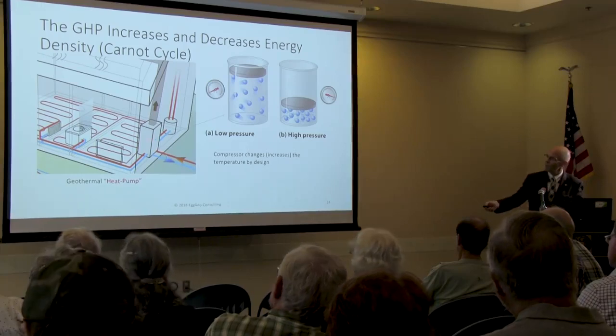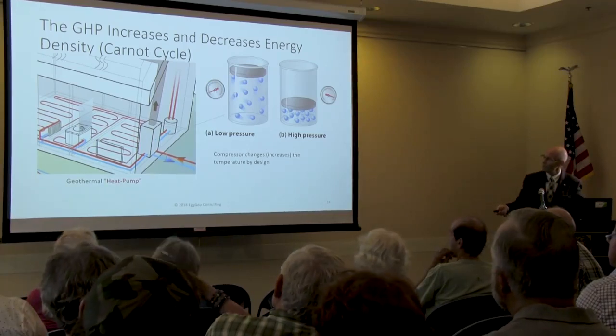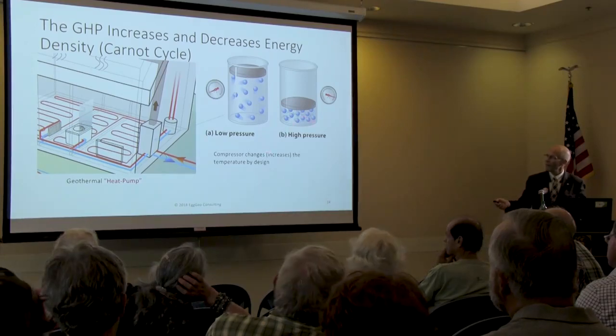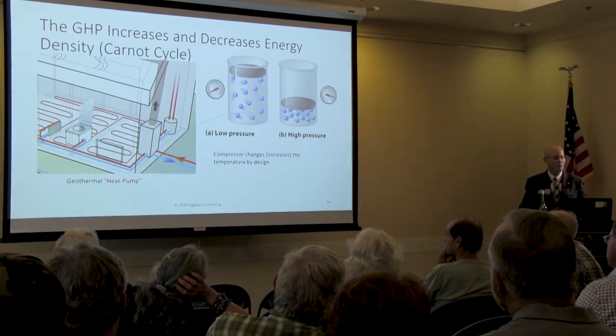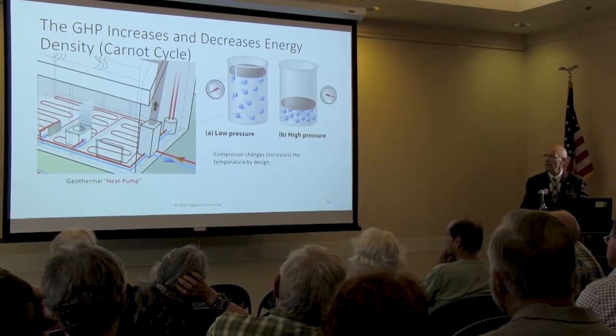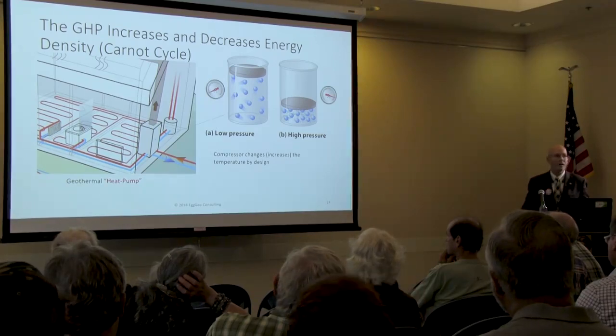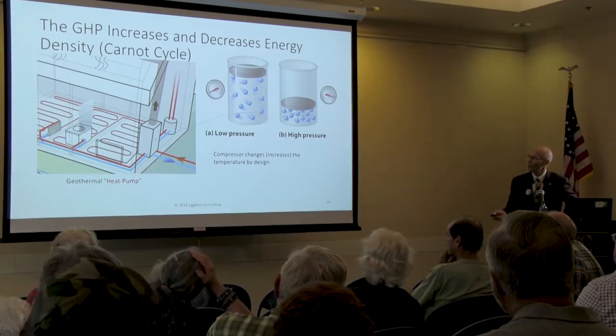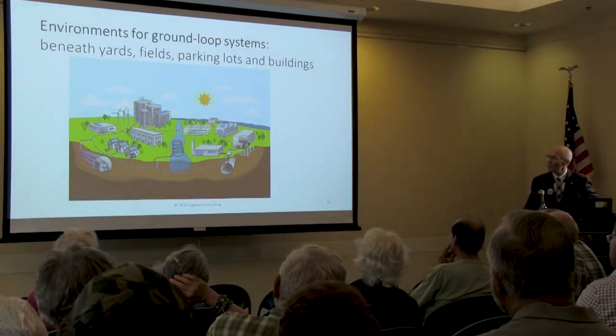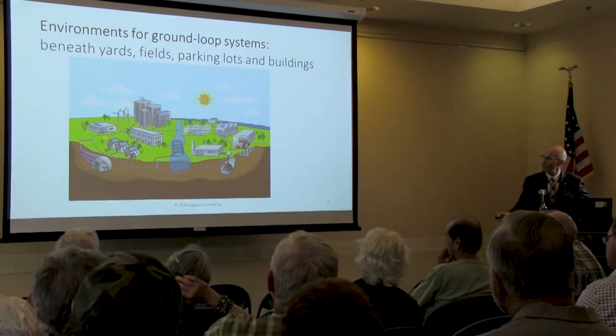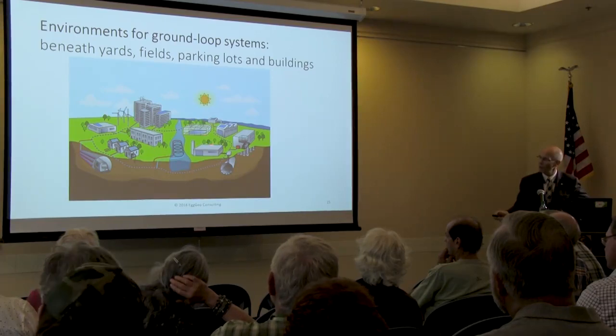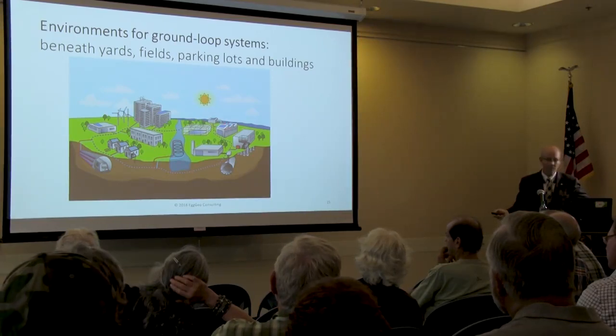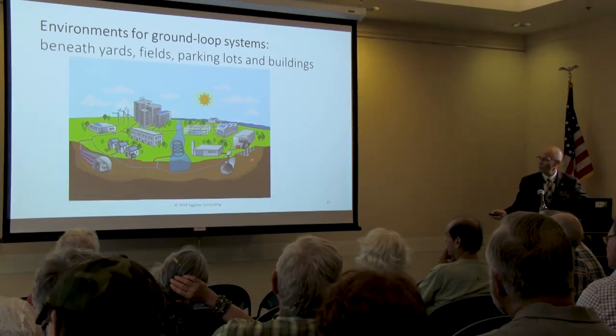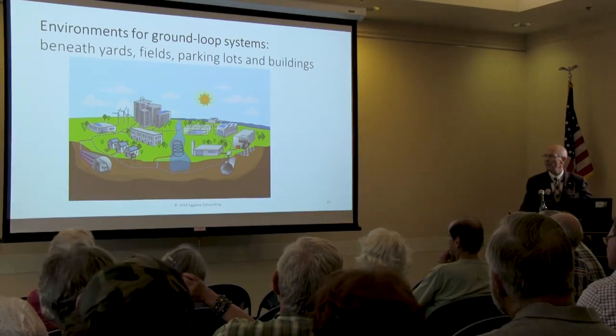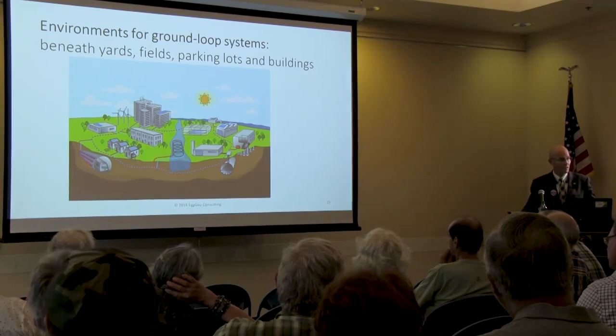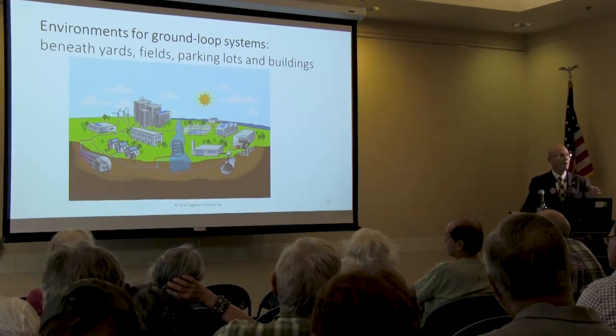And that's what this heat pump does right here, and it can deliver that whatever way we decide we want. And by the way, the delivery temperature here can be 90 degrees or it can be 190 degrees, and we'll talk a little bit more about that. It does affect efficiency the higher you go in temperature, but it's still a lot better than gas or direct or straight electric heating. So, some of the areas where we can use loop systems, this is a great pictorial representation. We can use waterways, such as this, even oceans. We can use building piles. There are many, many projects, including the new Google campus out in Northern California, all built on building piles.